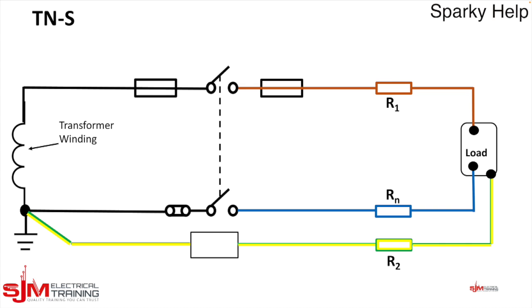Here we have the transformer winding as mentioned earlier. There's the star point of the transformer. This is the sheath of the supply cable because this is the return. There's the earth electrode for the transformer which the electricity companies will provide.